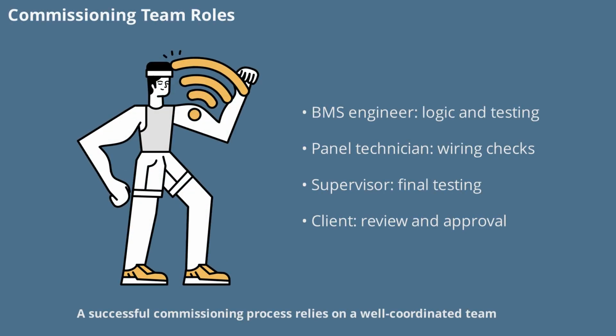A successful commissioning process relies on a well-coordinated team. The BMS engineer handles logic configuration and testing. Panel technicians focus on wiring and I/O verification. Supervisors or QA personnel oversee final testing and client demonstrations, while the client or consultant is responsible for review and approval. Clear roles and responsibilities ensure nothing is overlooked.